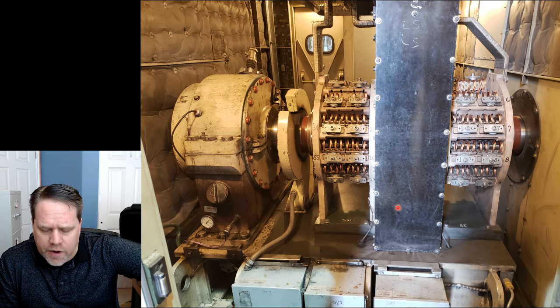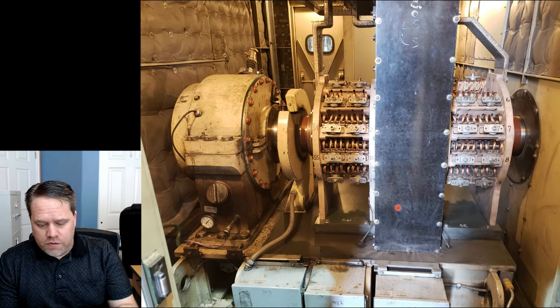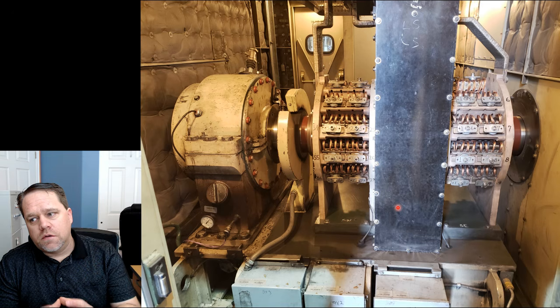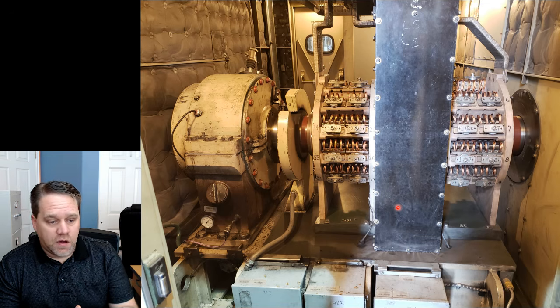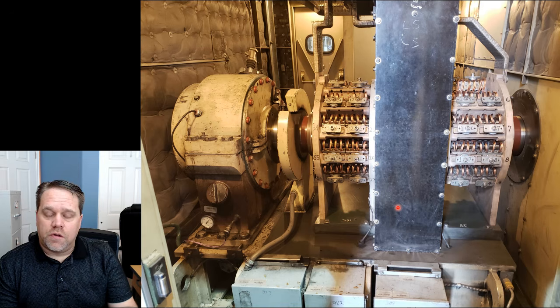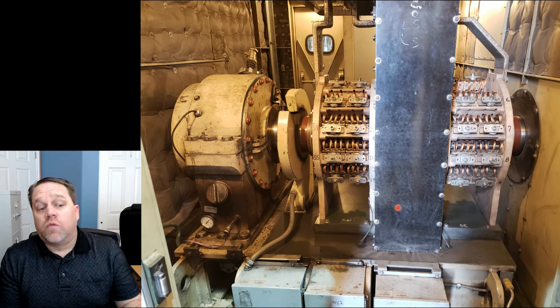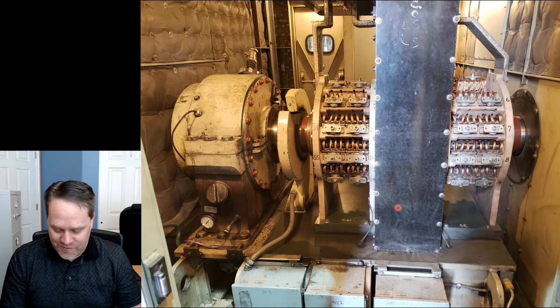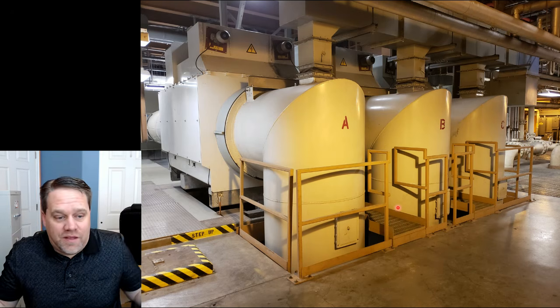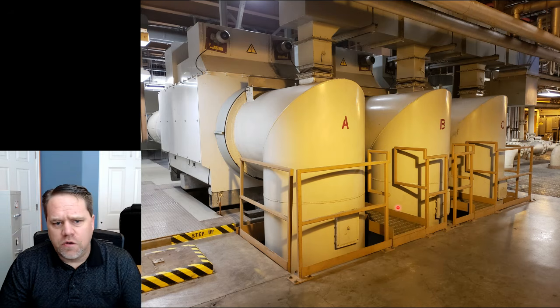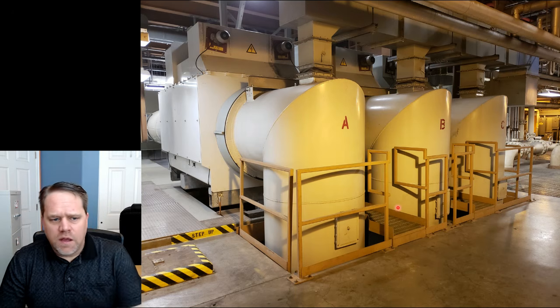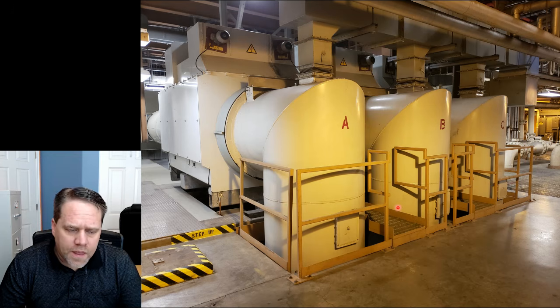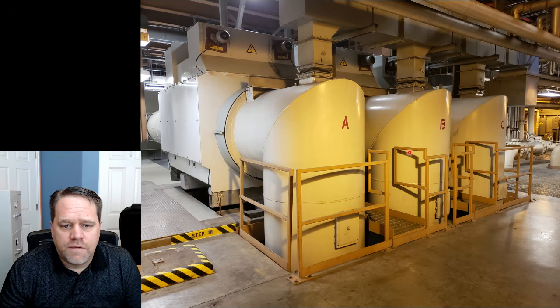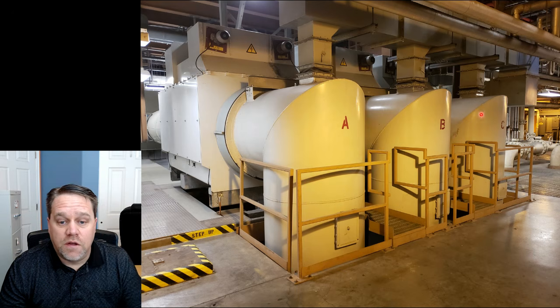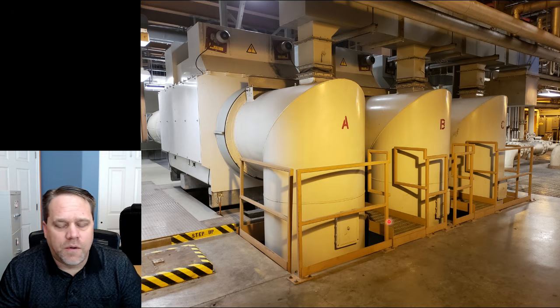So that's the generator. It's indoors, so how do I transmit 26,000 volts and 20,000 amps through a building, right? What size wire would you use to do that? Well, the answer is you don't use wire. They don't make wire that can do that. So you use what's called an isophase system, and each one of these here in the photographs, as you can see, we have phase A, phase B, and phase C. That is one circuit. Looking at those three, it's almost incomprehensible.